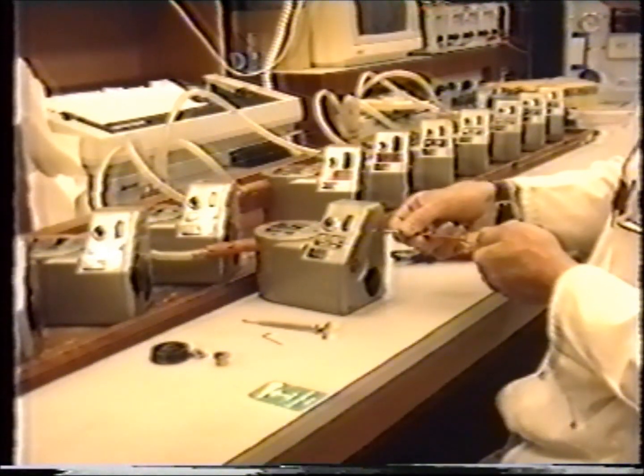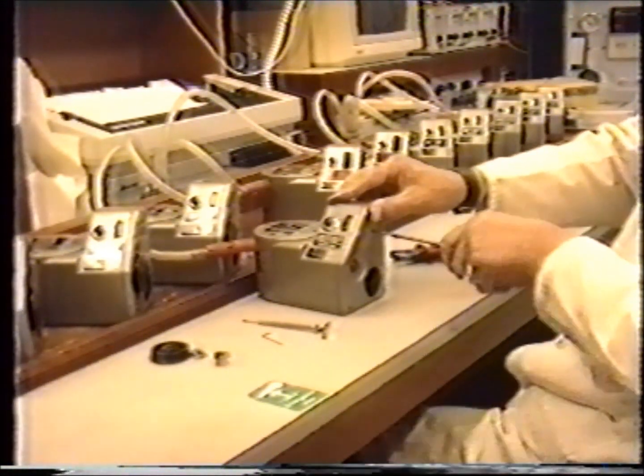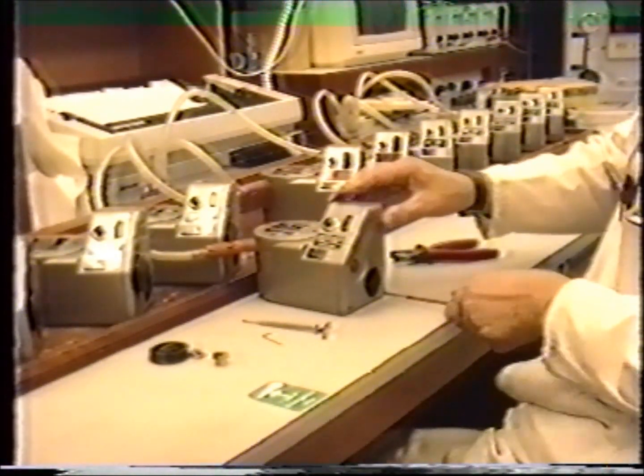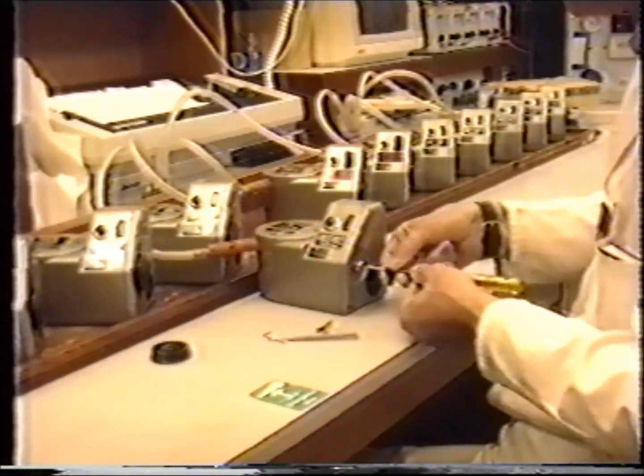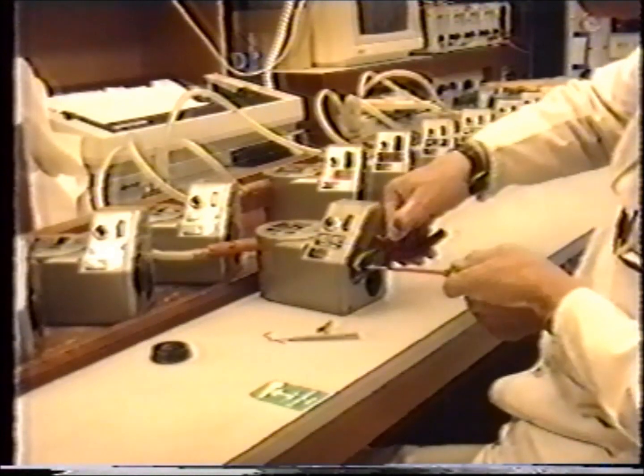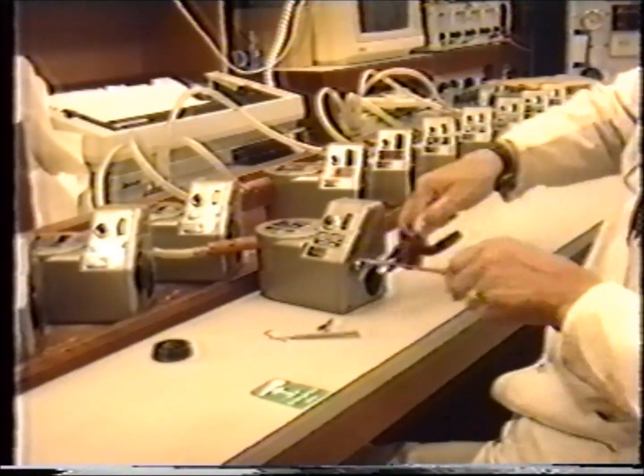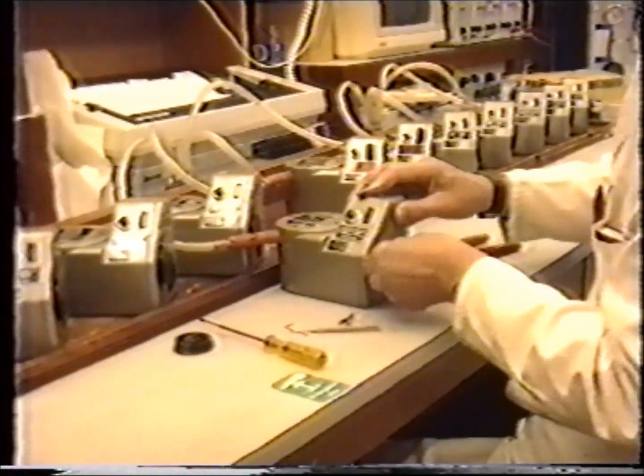A common outstation complaint is that the newly calibrated barometer just received from headquarters does not read the same as several others held at the outstation. This could be due to shocks suffered in transit or failing to allow the barometer to temperature stabilise. However, the usual reason is that the station barometers now read higher due to a slow drift upwards that occurs with time. It is therefore very important to follow correct procedures.